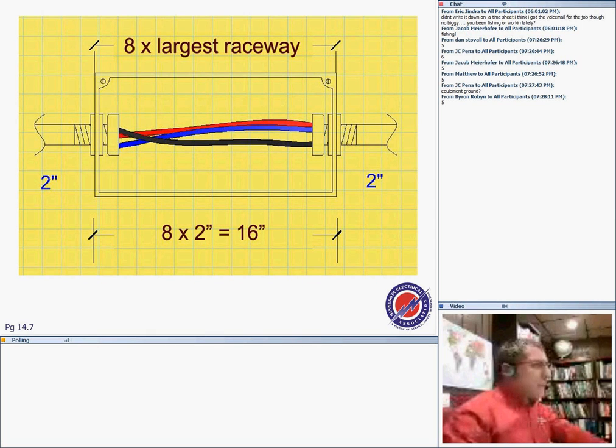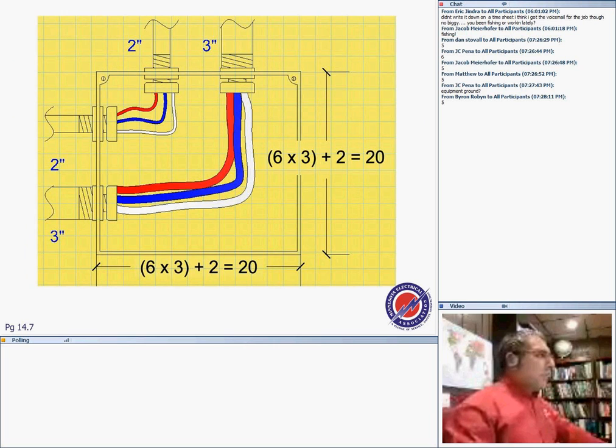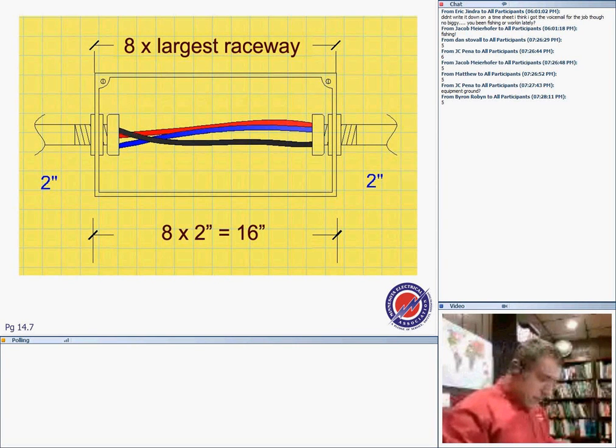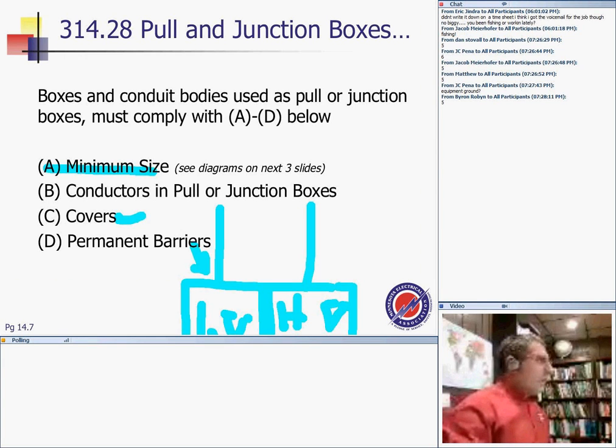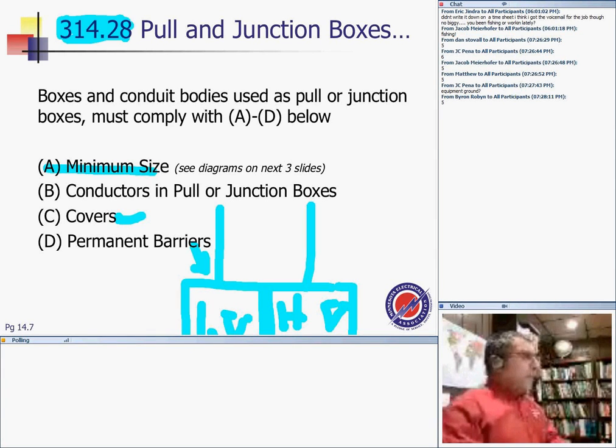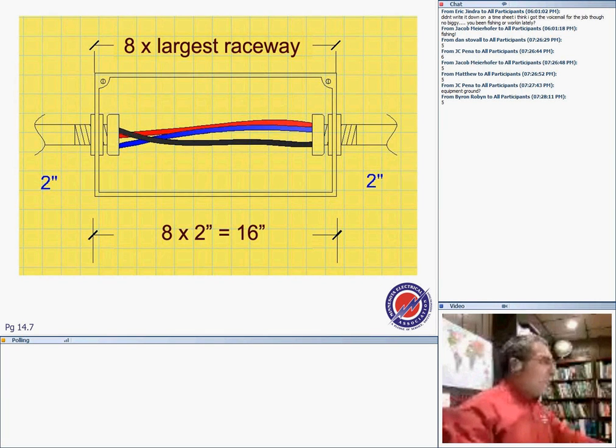Pull boxes, J boxes. It's a box that has at least a number 4 conductor or larger. With pull boxes, guys, we size them. There are a couple of rules you have to apply to the pull box, on page 173. This will be before that one, guys. This one, if you pass your journeyman exam, must be in your heart. Pull boxes are classified as a straight pull, as you can see. This one that you're looking at right here is a straight pull, right? Straight pull.